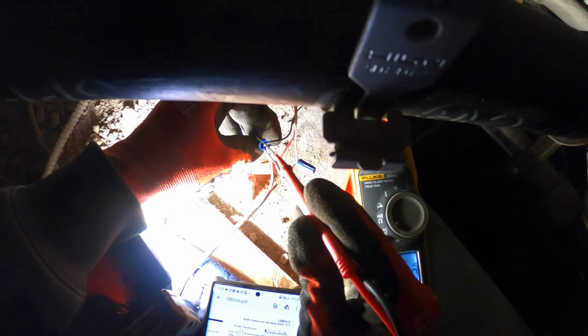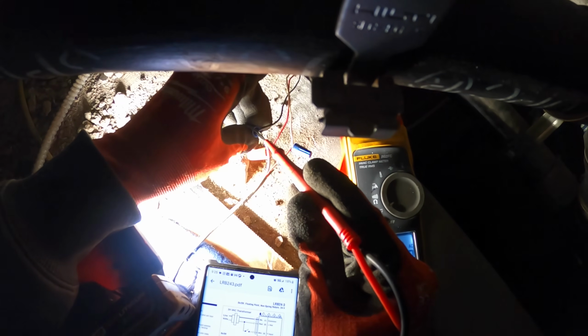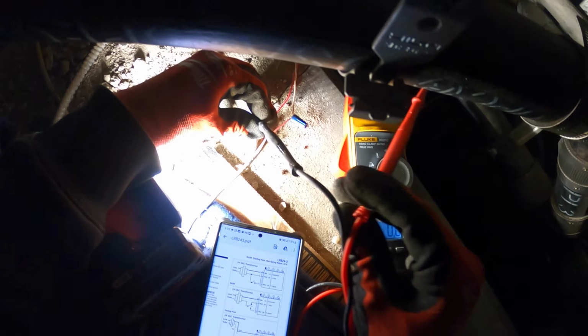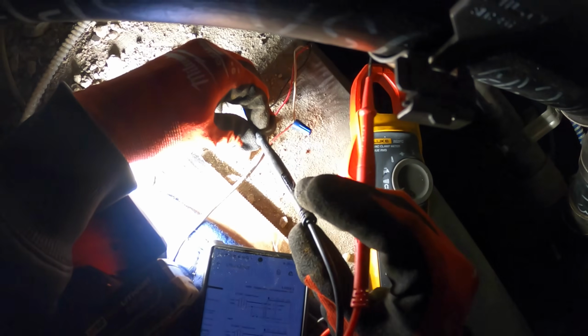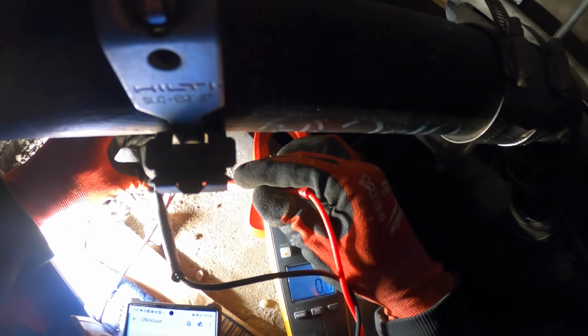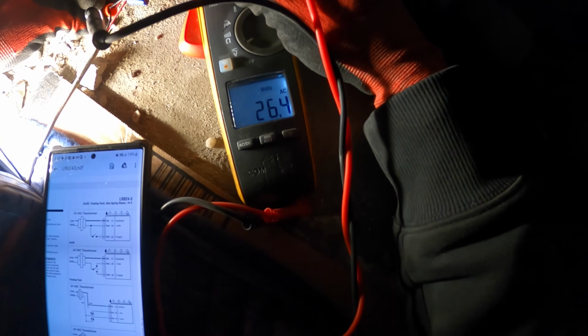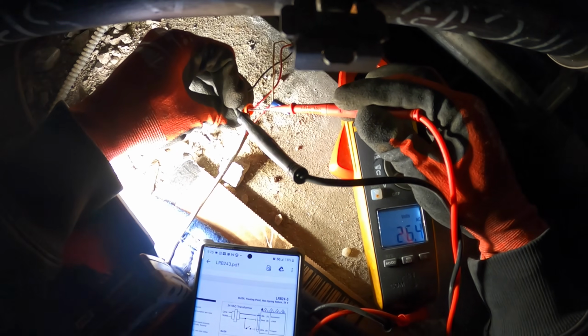Let's go ahead and test this real quick. The reason I'm up here is because I want to physically see the valve change. So black is common, let's get a meter in there. It says red is your hot, so there might be a steady 24 volts here all the time. I don't know, but right there we got 24 volts.